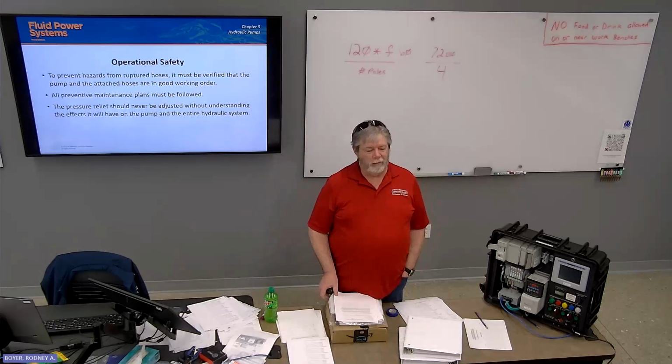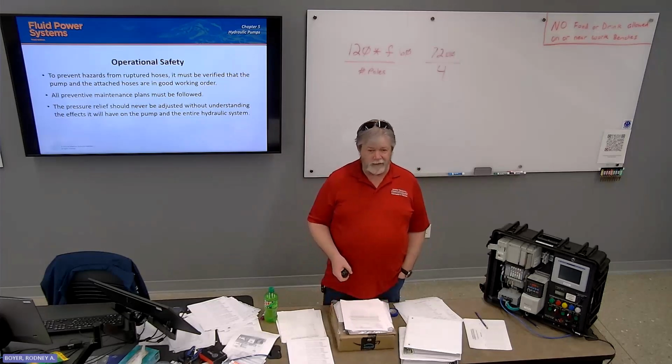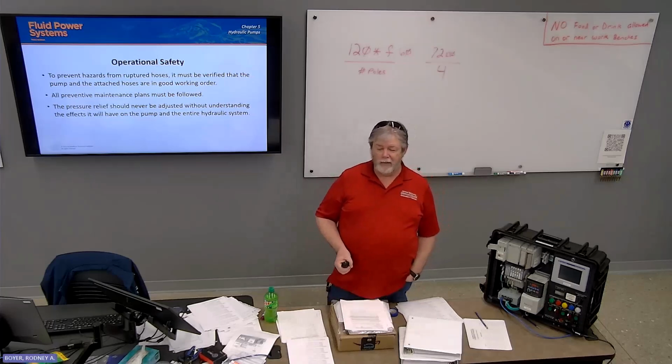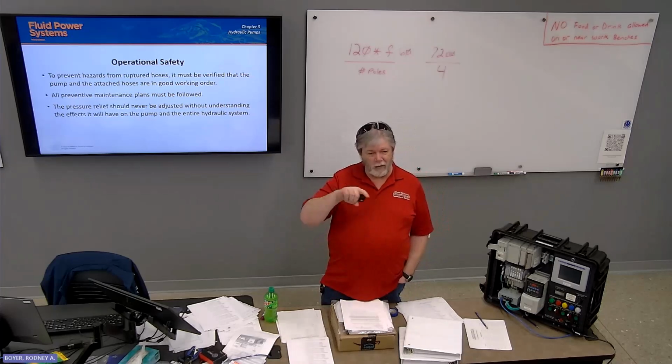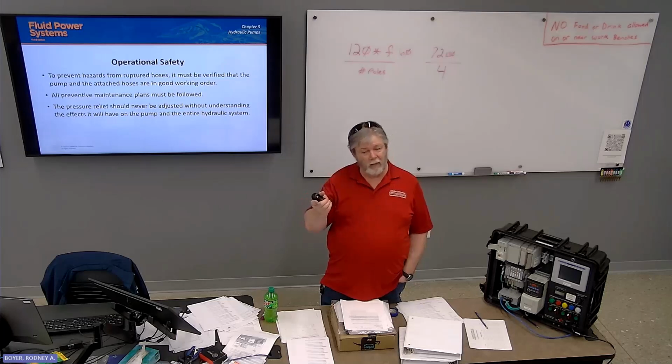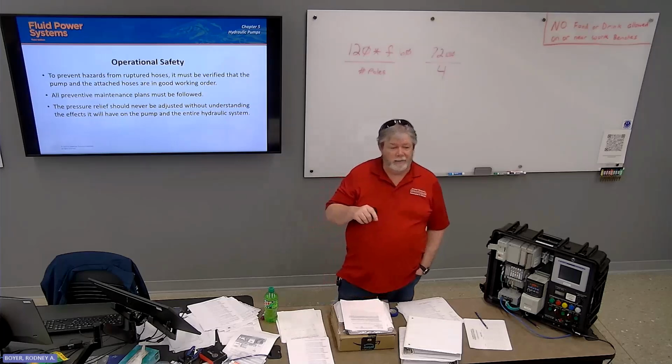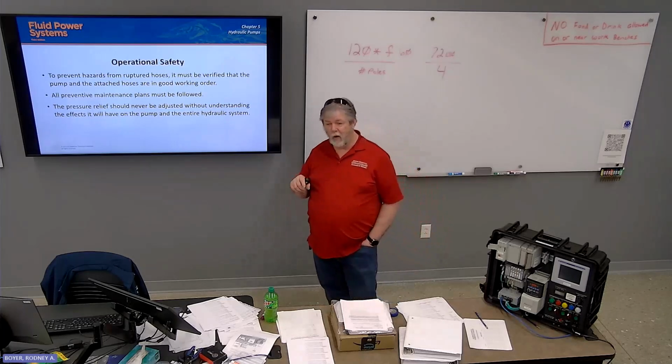Make sure that one is not dry rotting or other failures. And also make sure that every hose on it has a pressure rating on it. And make sure that it's at least 150% of what the pump is capable of. Maybe not what the pump is running at, but what it's capable of.